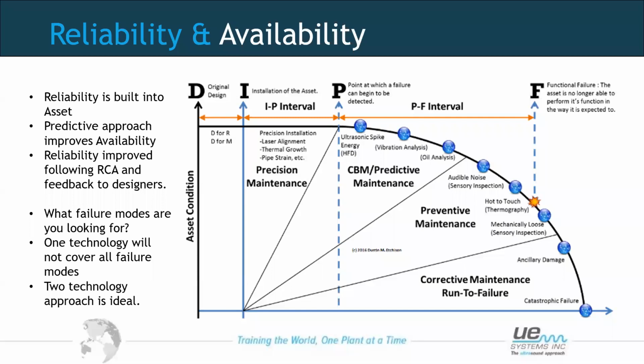And when we talk about the P to F curve, we're always looking at where we can detect a failure at its earliest. And it's universally known that one of the first changes in an asset when there is a potential problem occurring is a change in its ultrasonic emission. So if we're using ultrasound at an early stage with set baselines, we can detect the very smallest of changes, and then maybe use other technologies to help us confirm that.